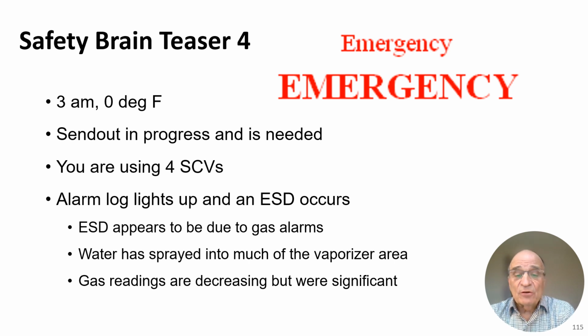Water has sprayed over much of your vaporization area. Gas readings were high, but they're now decreasing, but they were significantly high when the ESD occurred. What could be happening? Think about this. A hint there is that water was sprayed over much of your vaporizer area and that you're using submerged combustion vaporizers. But there are a number of scenarios that this could be related to. You've got to think it out and see what ideas you come up with.